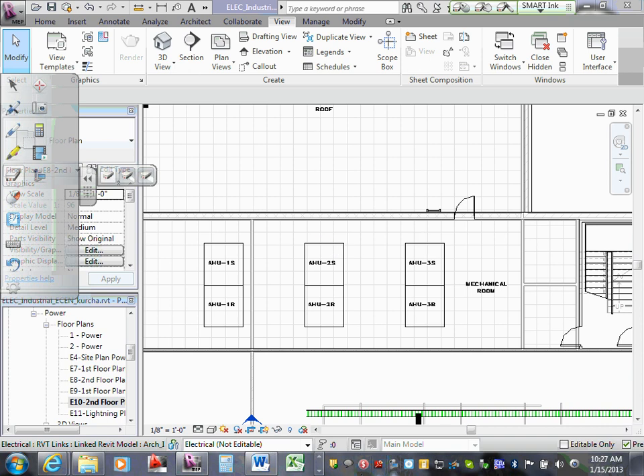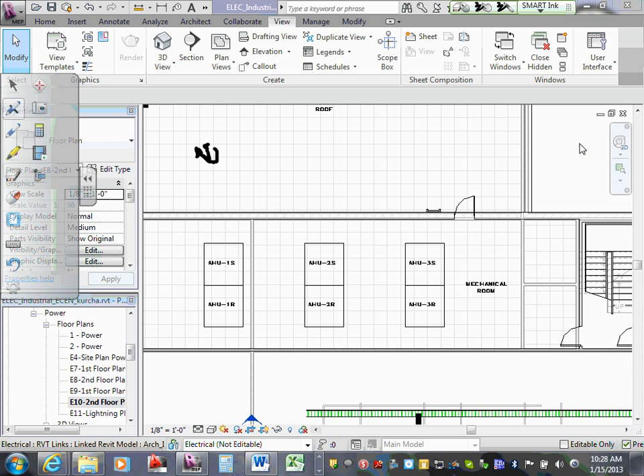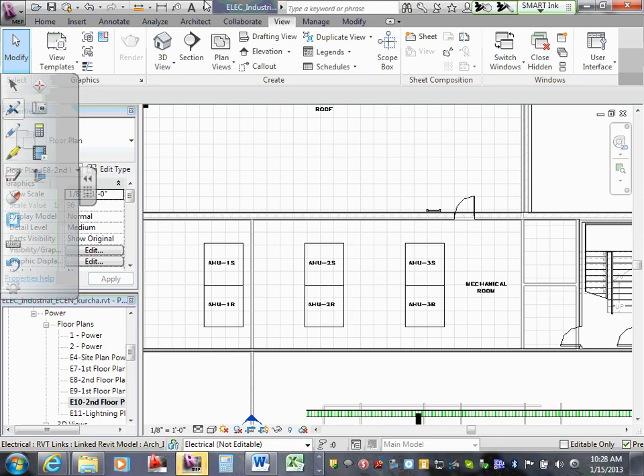You think right there. No, that's fine. Each duct smoke detector. It's there. Yeah. Here's your duct smoke detector. With each duct smoke detector, you're going to have a control module, a relay module, and more than likely you're going to have a remote test switch.